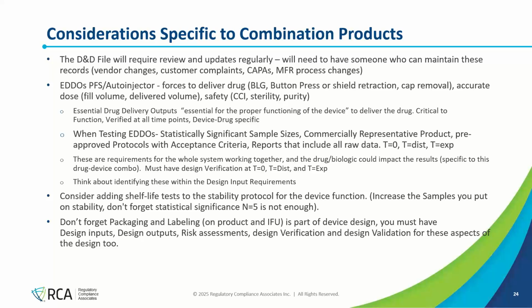Definitely want to define these early in the development process. So you want these to be clearly identified within your design input requirements, because this is the majority of the design verification testing you'll have to do for a combination product. I want you to think about maybe adding your shelf life tests for the device, which would be T equals expiry date, to your stability protocol. You're already putting massive amounts of product up on stability, either accelerated or real time, for the drug purity, contents, etc. If you put enough finished devices up there, you can also pull those for your shelf life samples. So definitely consider that since you're already doing that for the drug.